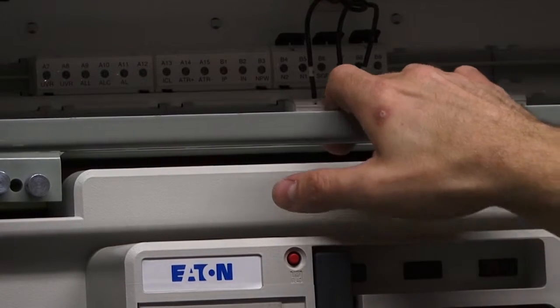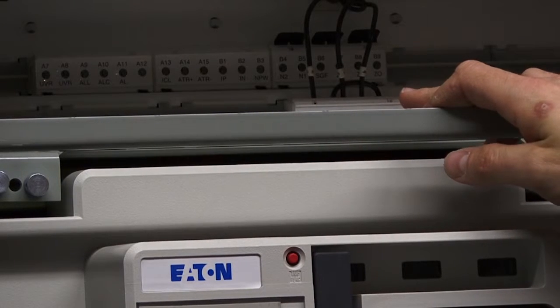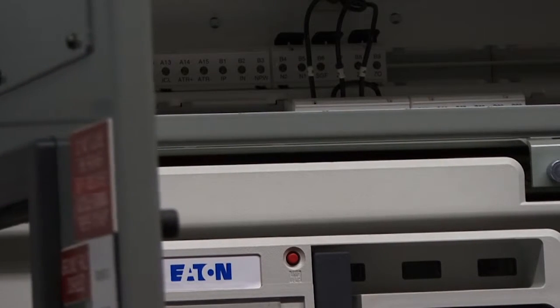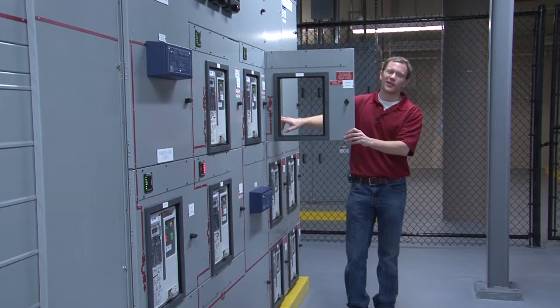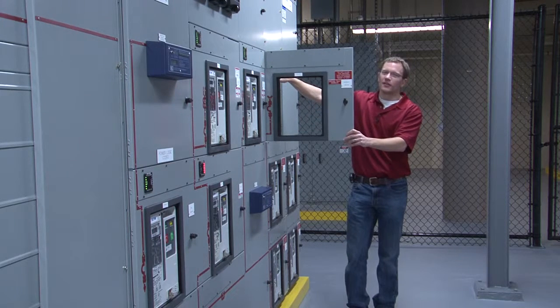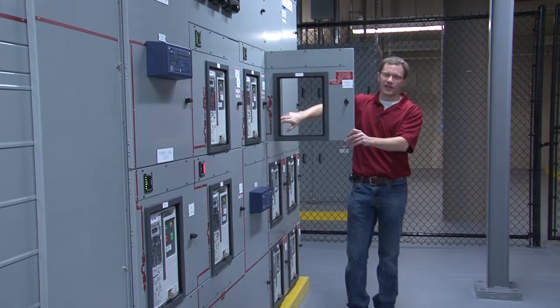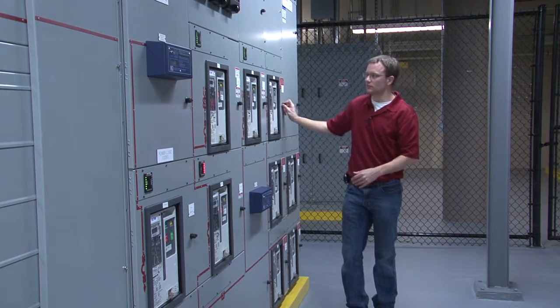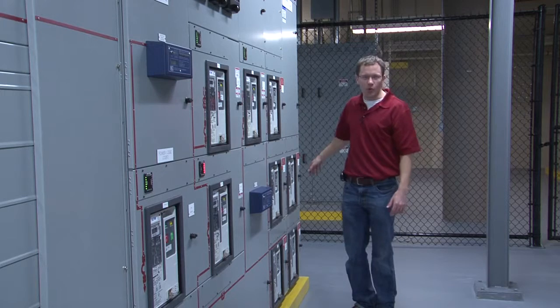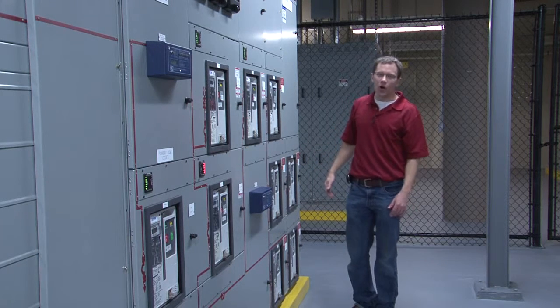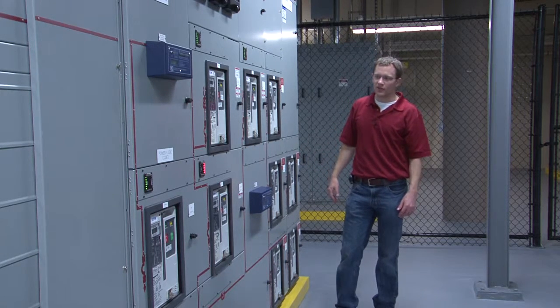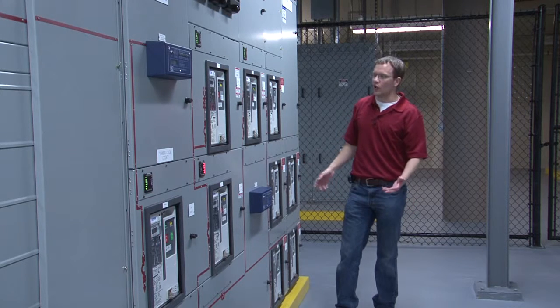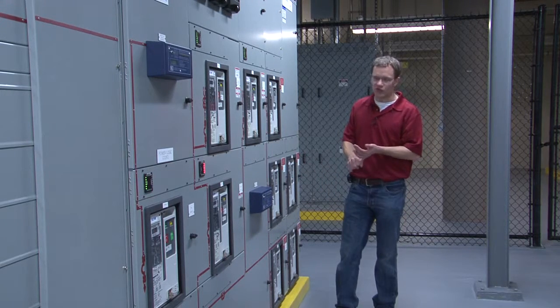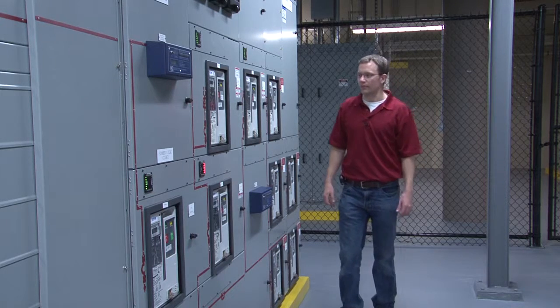And I guess these wires here are the wires that go back to tell the UPS that's associated with this breaker, that this breaker is closed or open. So these wires here just communicate information back to the module about the state of this breaker. If any of these breakers opens for any reason, an alarm will be annunciated on Convergent. So if they're just not closed, if they're either tripped or just not in their normal state, which is closed, it'll annunciate an alarm.